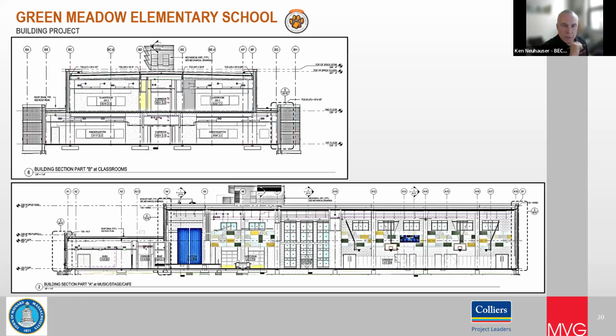I may be following the point you were just making. I'm looking at the responses about 2-pipe, 4-pipe systems. I believe the DOAS units and rooftop units are all 4-pipe systems, from what I understand. So that's how the building may be in heating mode, but there's still chilled water going to the air handlers to provide dehumidification, and if needed we can send cooler than neutral air through those systems. Is that what you were suggesting about flexibility on the ventilation side?